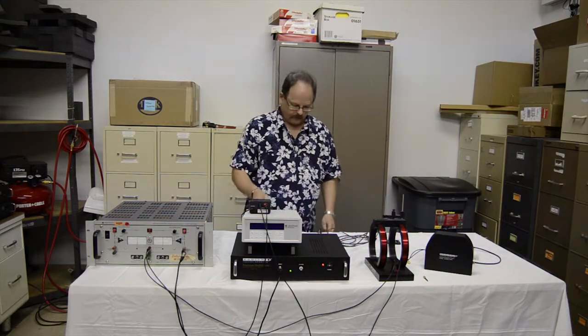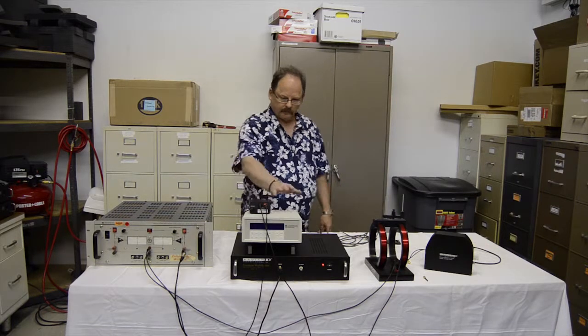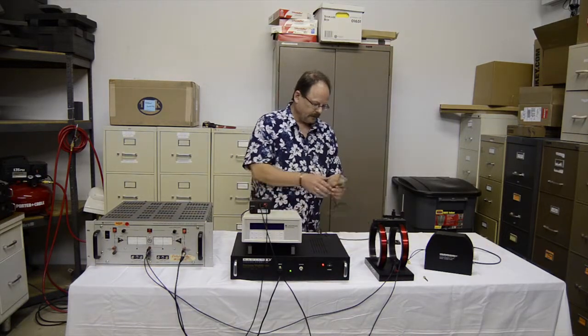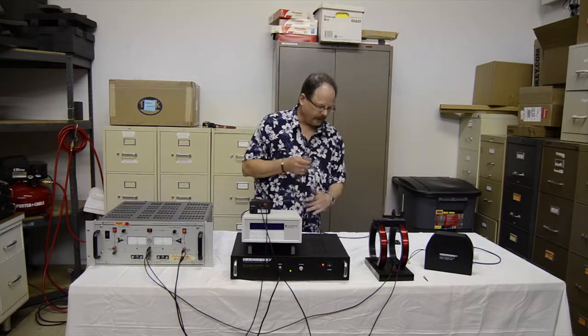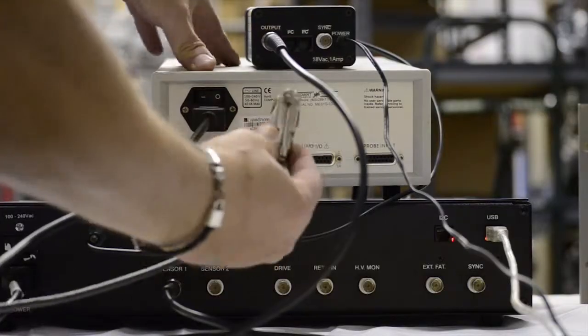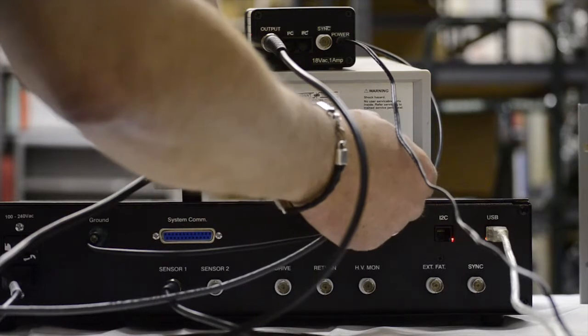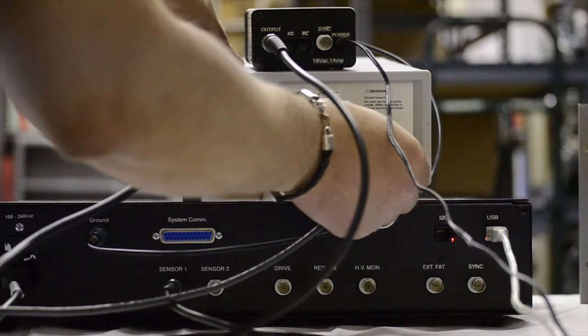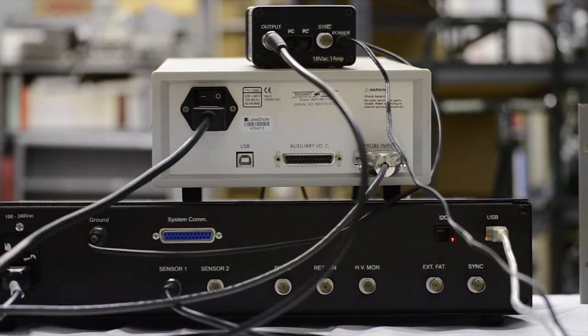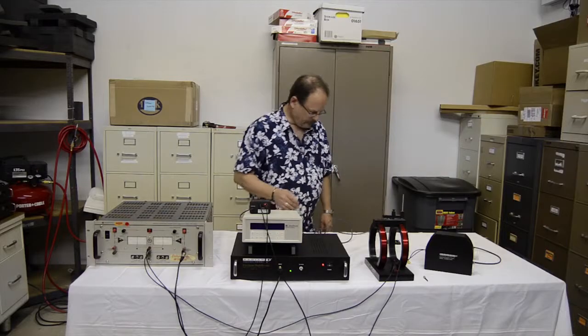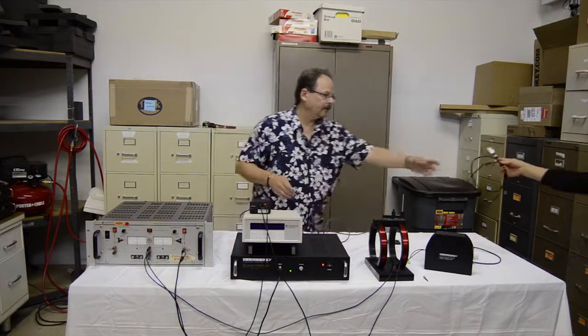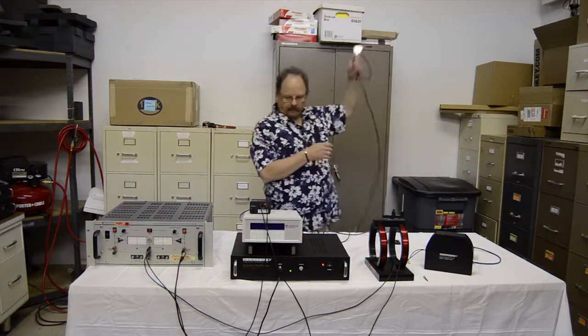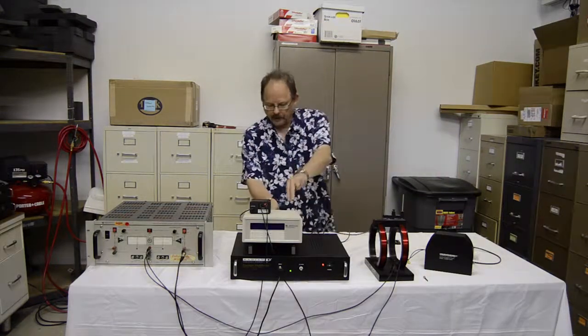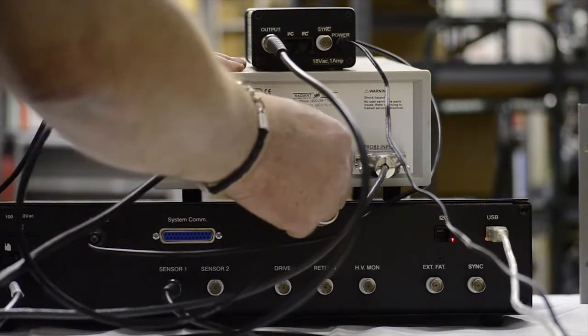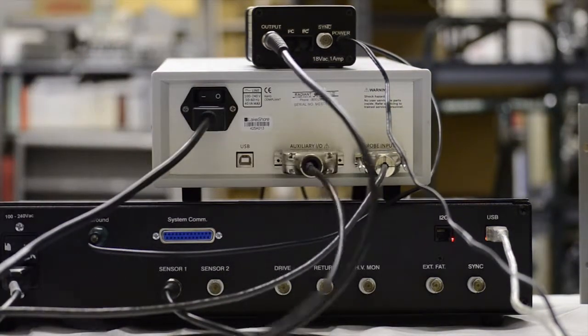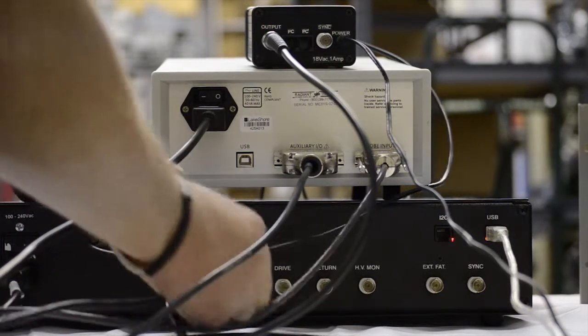The next thing we need to do is connect the Gauss meter up. The Gauss meter sensor wand is connected into the probe input at the rear panel of the actual Gauss meter controller box. Then, with the connector that was provided, we take the aux IO port of the rear panel of the Gauss meter box. The BNC end goes into the sensor 2 port of the tester.